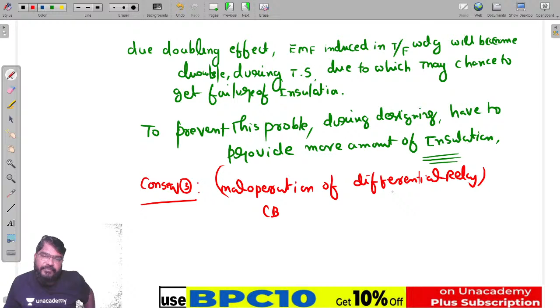Differential relay is used for protection of the transformer. So the relay will be operated due to high magnetizing current at the time of switching. This is malfunction of the differential relay. Is all of it clear? So these are the consequences of the doubling effect.